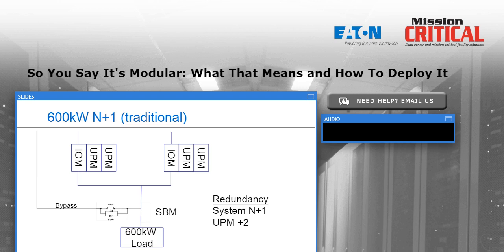So the UPSs would come to the system bypass module where their outputs would be tied together in parallel, and I have 2 600 kilowatt UPSs, 2 sets of 600 kilowatt batteries, and only 1 600 kilowatt critical load. But the idea is if a problem develops in either UPS, the other UPS is big enough to handle the capability. And in a modular system like this, you see I could suffer the loss of 1 UPM on the left-hand side UPS, and if I'm having a really bad day, I could suffer the subsequent loss of a UPM over on the right-hand side. That would still leave me between the 2 UPSs with 2 300 kilowatt UPMs available and running that could support that 600 kilowatt load. So my mission critical redundancy there would actually be N+2 in this traditional type situation using modular UPSs.